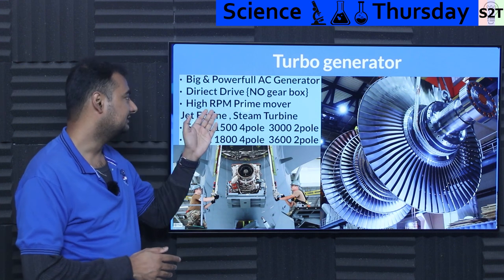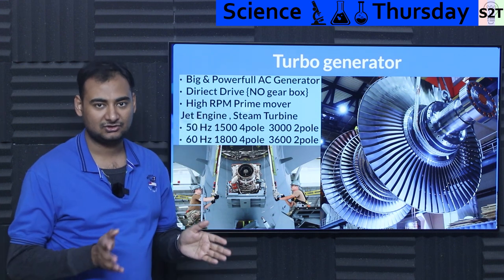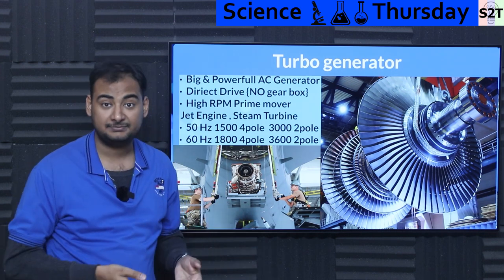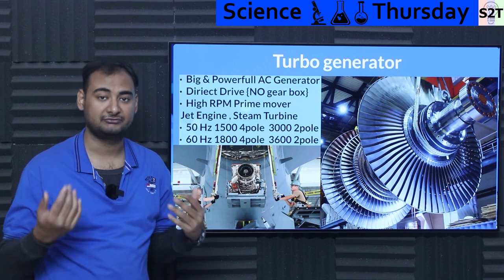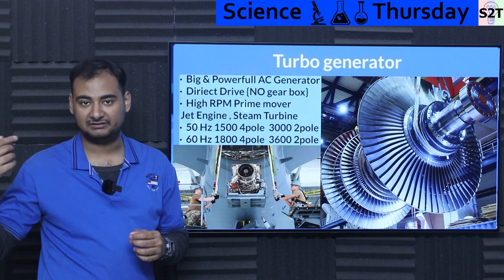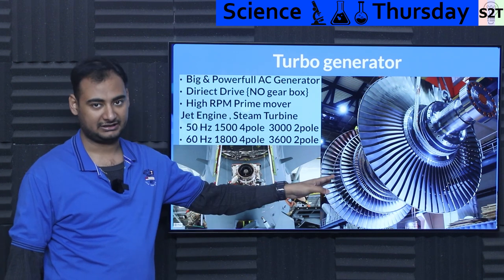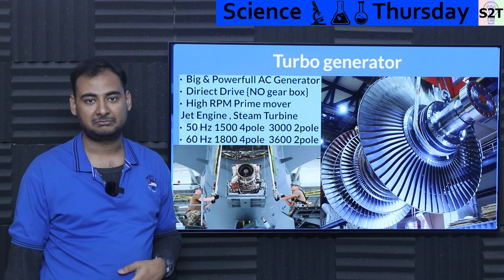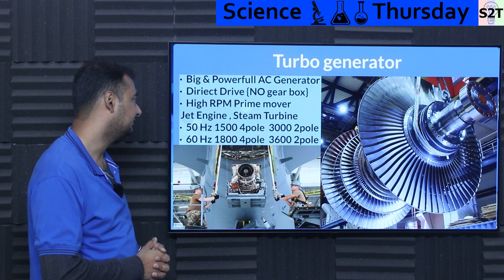The core component is direct drive — meaning there is no gearbox between the prime mover and the generator. In many cases you could have prime movers with very high or very low RPM. For example, in wind turbines the RPM could be very low, so you'd use a gearbox. Here, you don't do that — you direct drive. If your steam turbine is rotating at 3600 RPM, you just direct drive it. That's a Turbo Generator — generally high RPM machines.